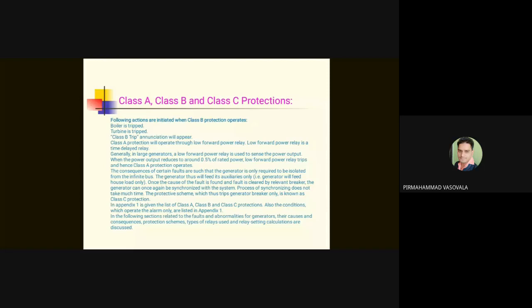Class C is very simple protection. Class C is when there is a fault on the line. Generator, then generator breaker, and then there is a bus. From the bus, many lines are emanating, some 8-10 lines. On one of the lines, there is a ground fault or line-to-line fault. So if there is any kind of ground fault or line-to-line fault, the line relays must operate.